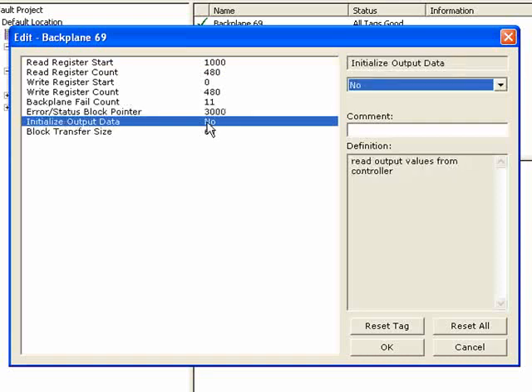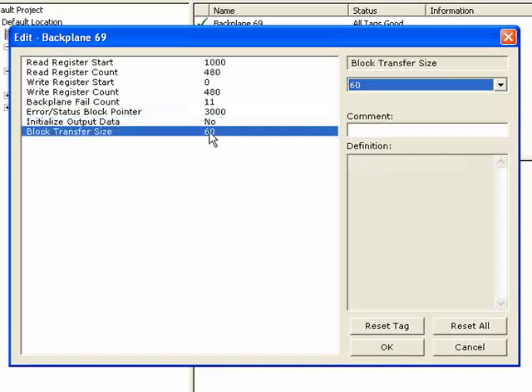Then you have the initialized output data. What it does is allow the module to get values from the controller before starting any Modbus communications. When you cycle power to the module — say with the cold or warm boot bit within ladder — that zeroes out the module's database, and Modbus communication starts, which may send zeros where there should be data. With this parameter set, it'll get values from the controller before sending any Modbus data. Then you have the block transfer size, which defines how many data words per block are sent between the module and the CPU. This parameter has no bearing on your Modbus network — it's only for communications between the CPU and the MVI69 MCM.